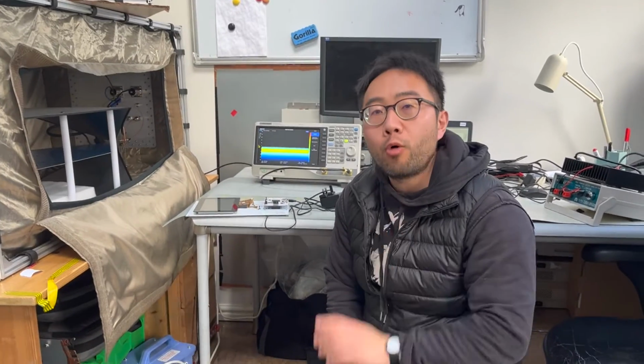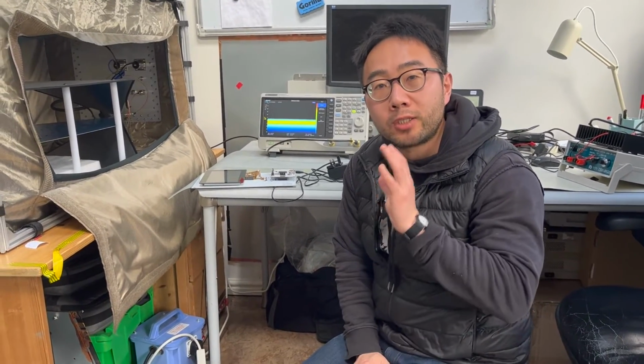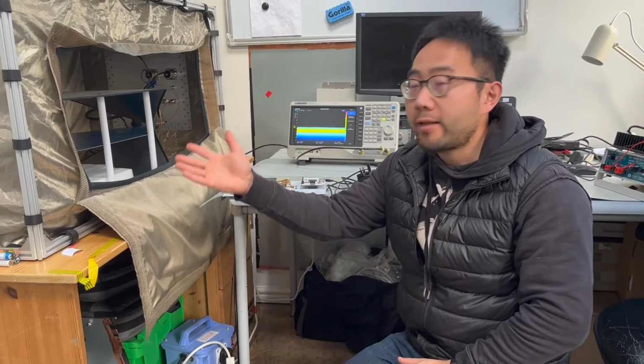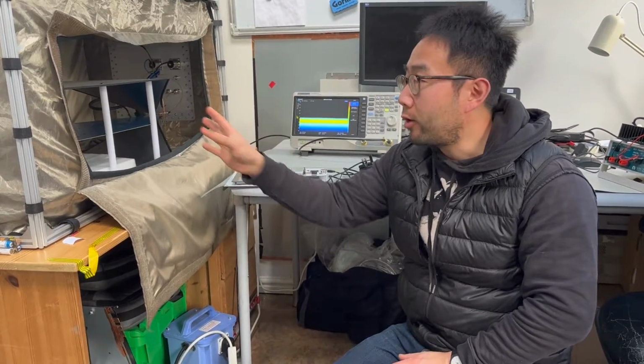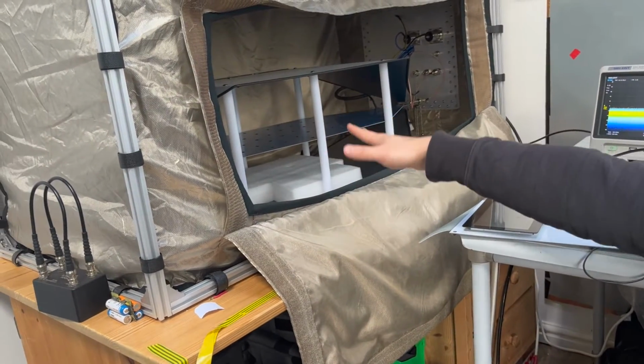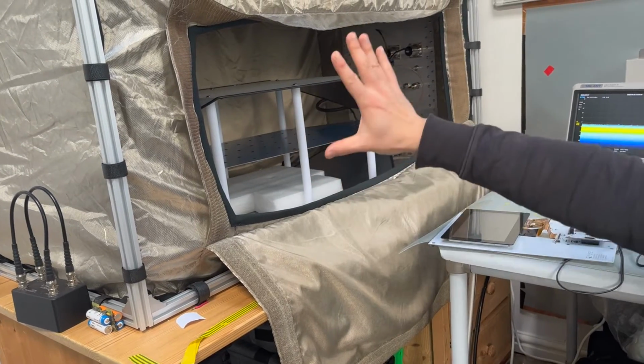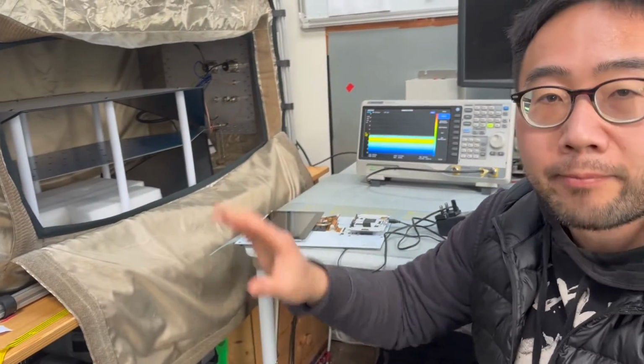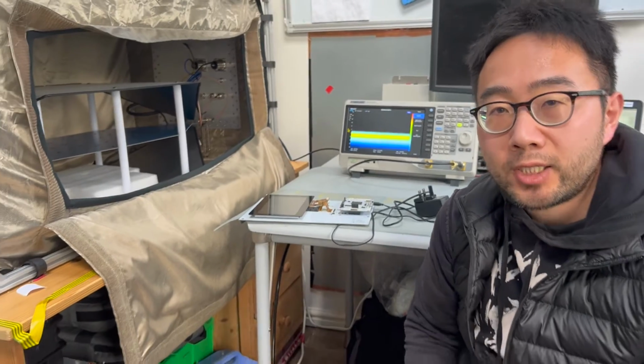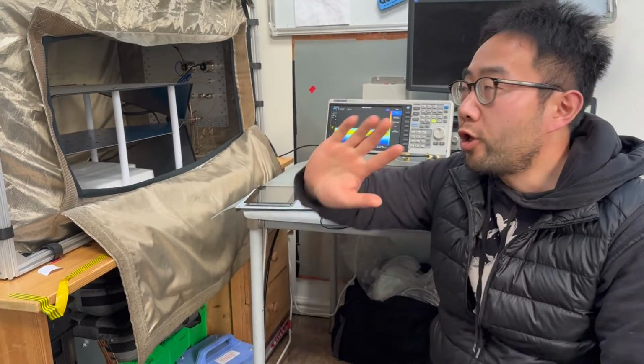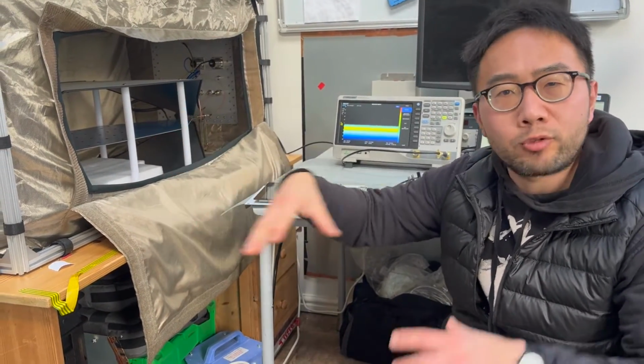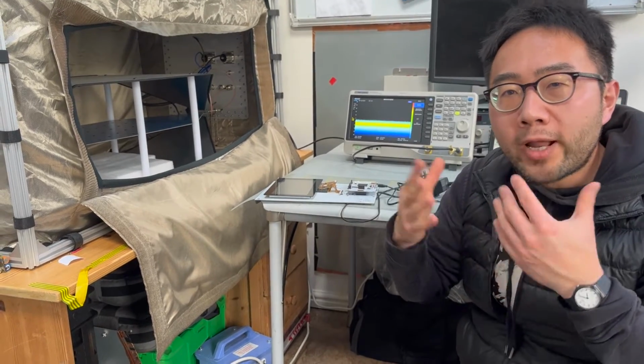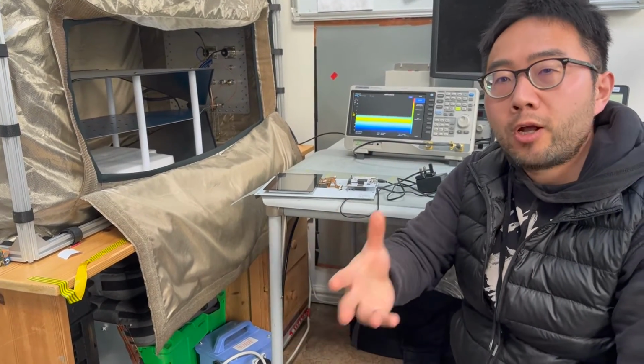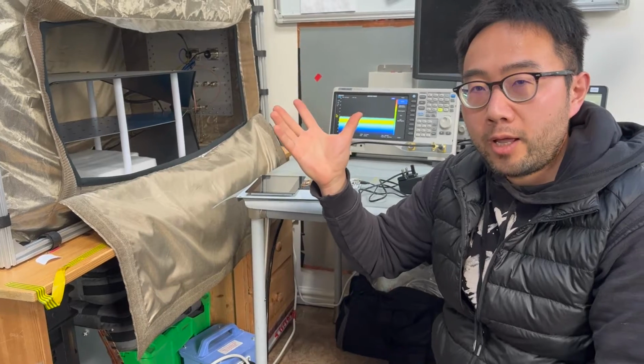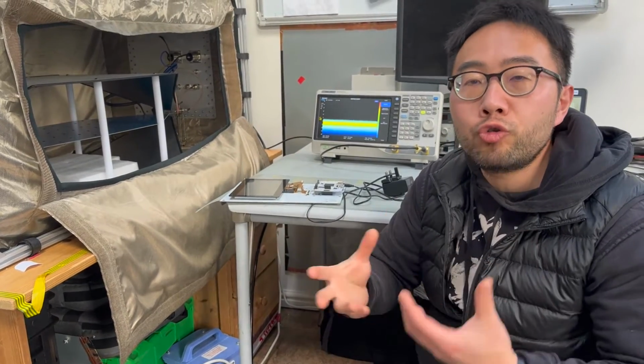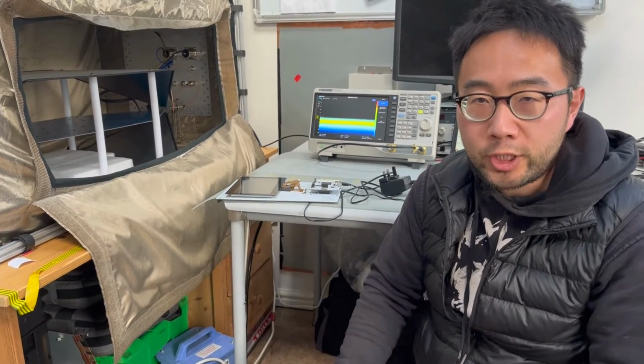The first step I often do is to test the DUT inside the TEM cell. So I'm going to put the DUT inside the TEM cell, then close it and perform a scan. The benefit of doing this is that it gives you a benchmark, because we know what is inside the TEM cell is really quiet. So whatever spectrum or spurious results you get, you know it is the true EMI coming from the DUT.